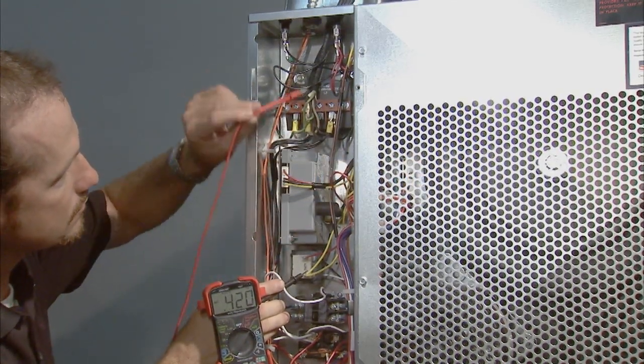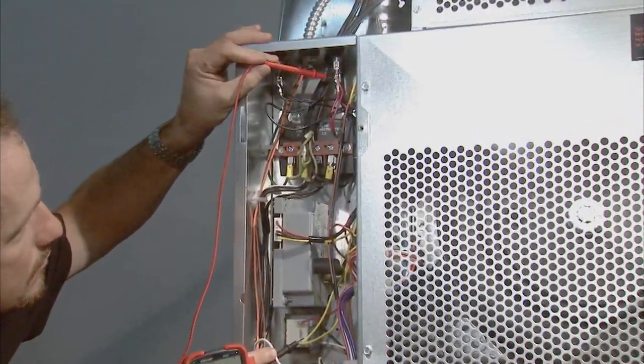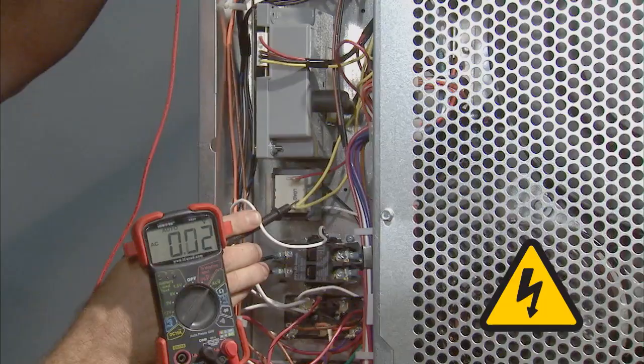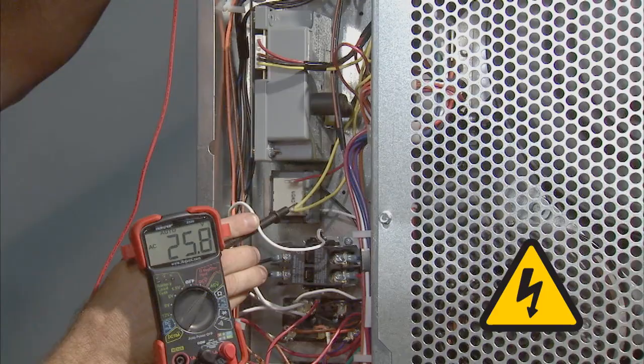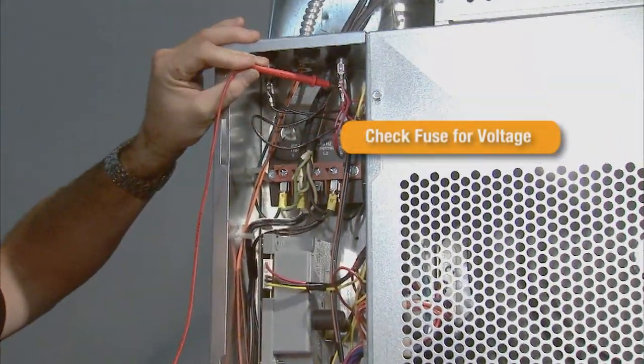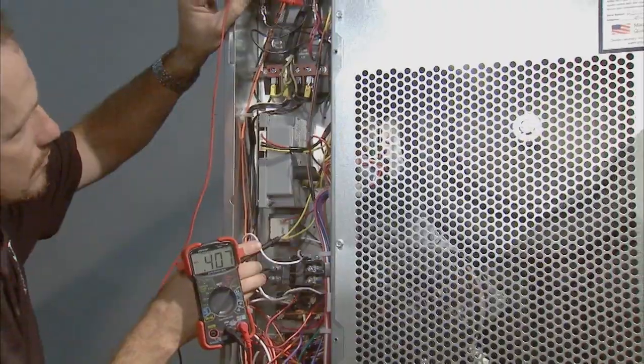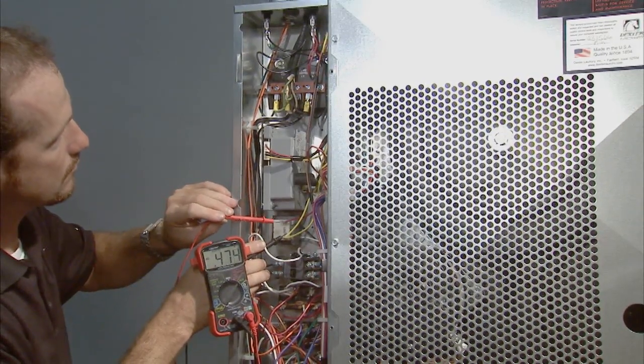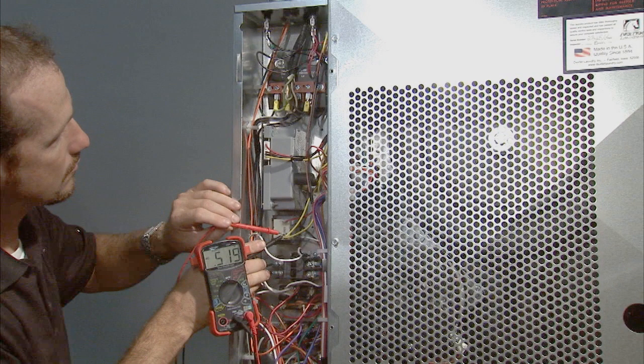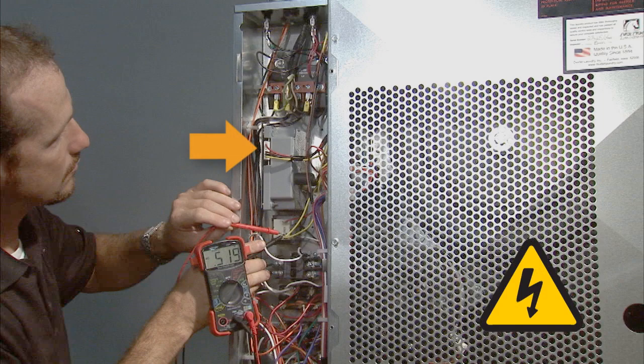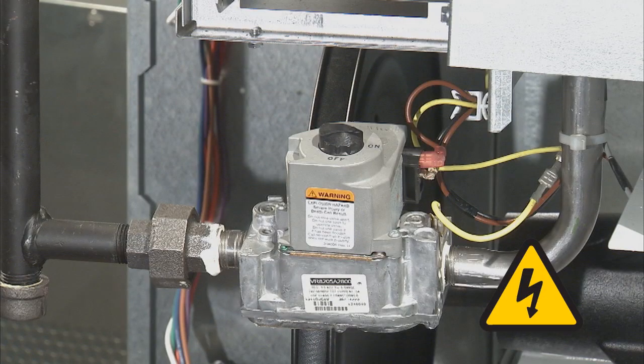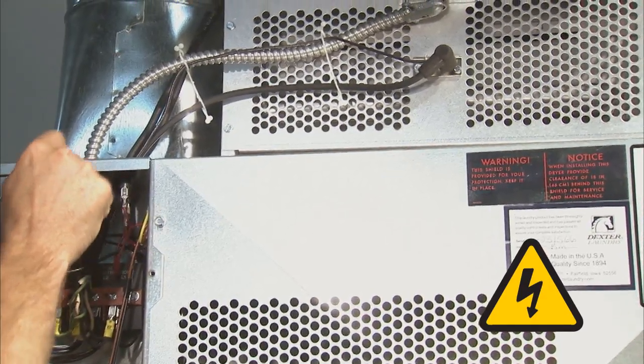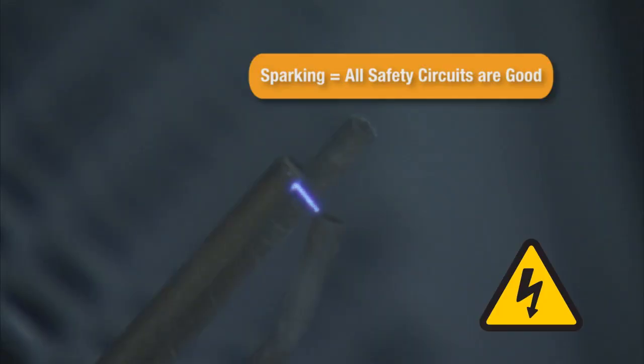The 24 volts now travels down the red wire to the 1.5 amp fuse. With the black meter lead on the yellow neutral wire, check for 24 volts AC on both sides of the fuse. If there is no voltage exiting the fuse, replace the fuse or possibly the fuse holder. Two events occur when 24 volts reaches the ignition module. First, the unit will send voltage to the gas valve. Then the unit will send high voltage to create a spark at the igniter.